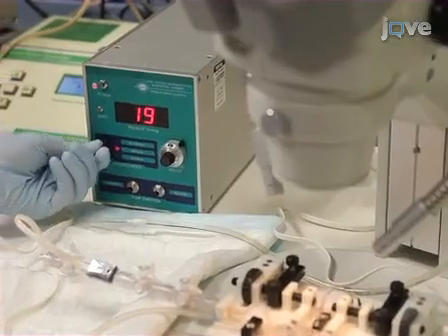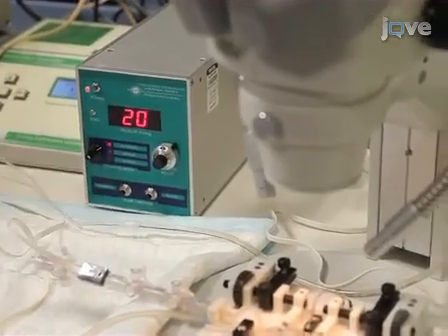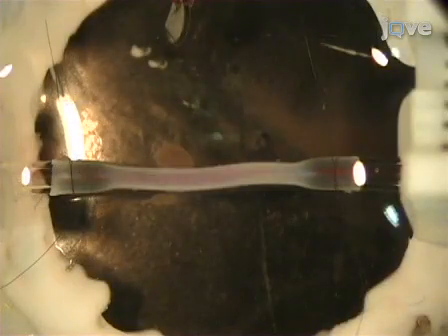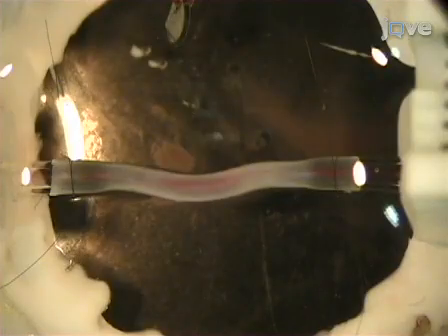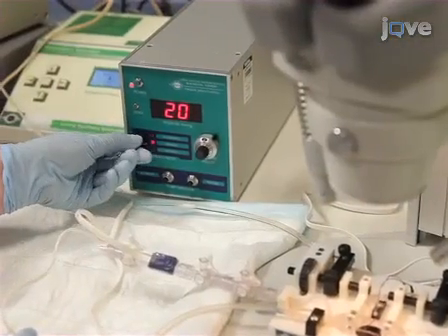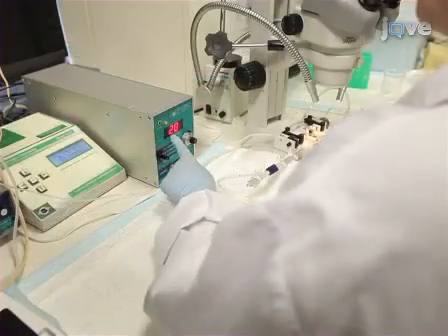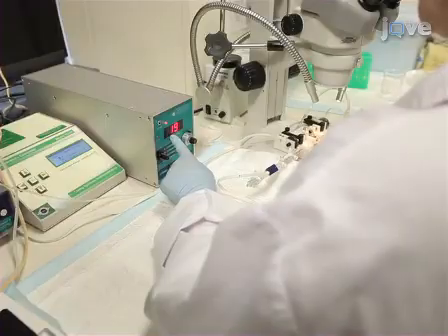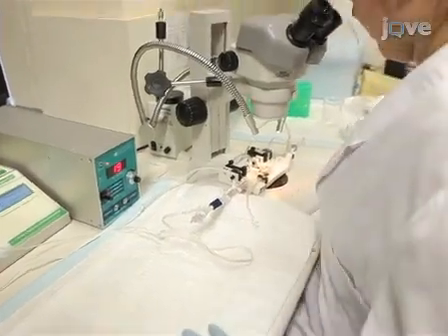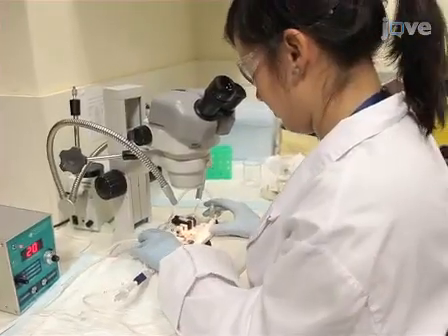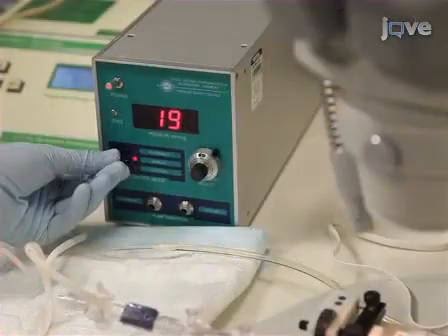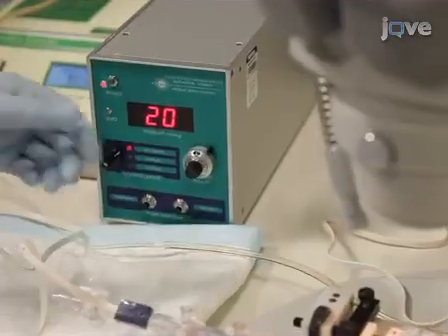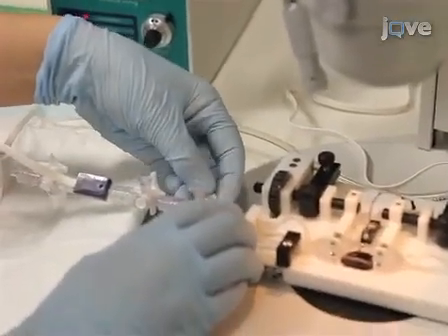Adjust the pressure servo back to automatic, then open P2 to the chamber. Under the microscope, observe the vessel dilate when the tap is open to the chamber. Switch the pressure servo to manual. Again, check for any decreases in pressure. If a drop in pressure continues, then the system is not pressure tight and there's likely to be a hole in the vessel. Switch back to automatic and open P1 to the chamber.